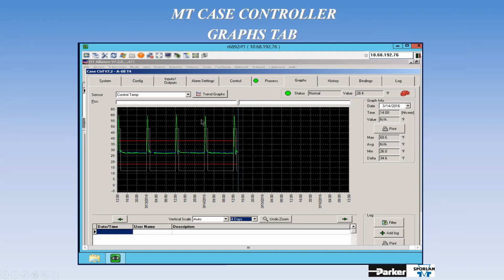Now I go into defrost. You see how high my temperature spikes? I come out of defrost and boom, I drop like a rock. Why? Because I've tweaked my pull down setting to get a super fast pull down, yet I never blow past the set point and trigger a low temperature alarm. So that is what you want to see.